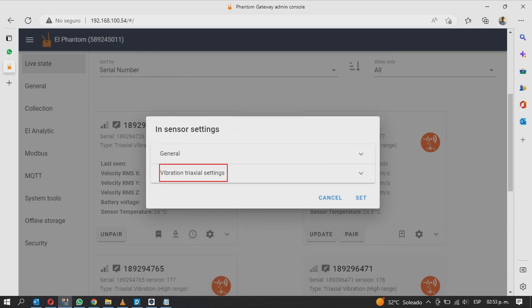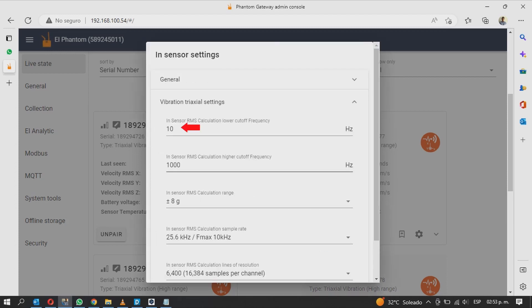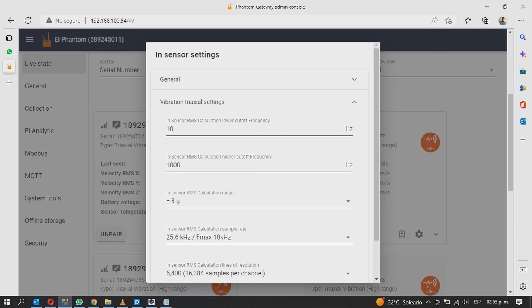Finally, under vibration triaxial settings, you will see the frequency range with which the Phantom sensor RMS values are calculated. According to the standard, the range goes from 10 to 1000 Hz, but you can change it if you wish.